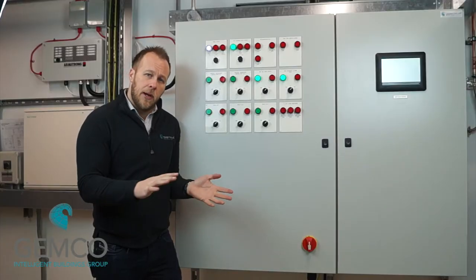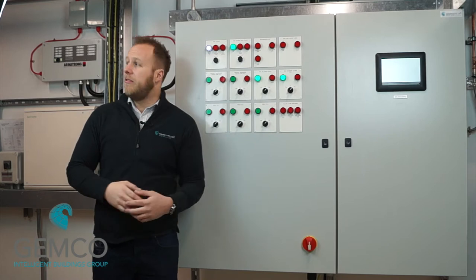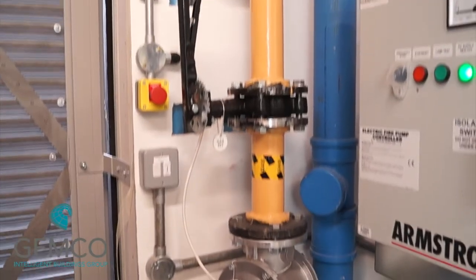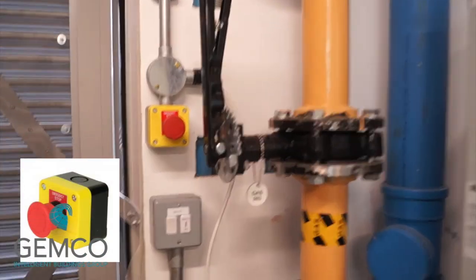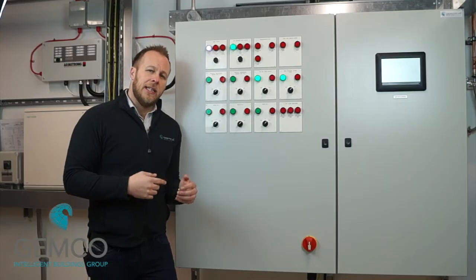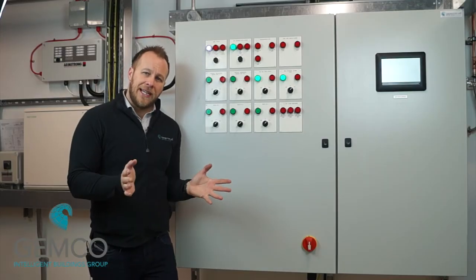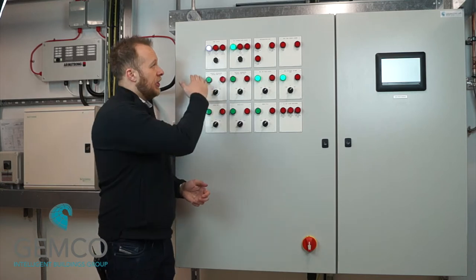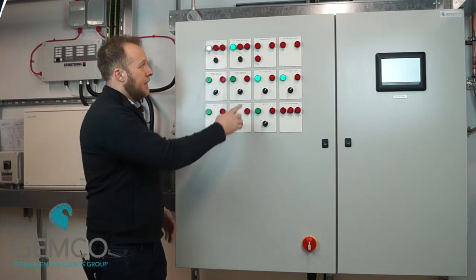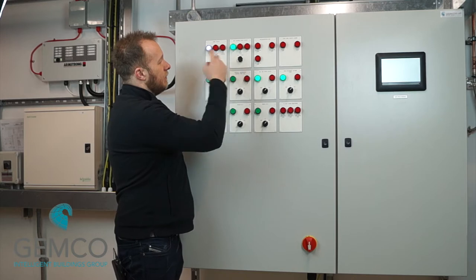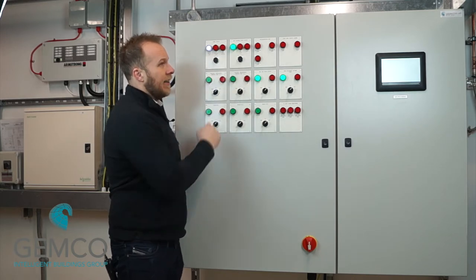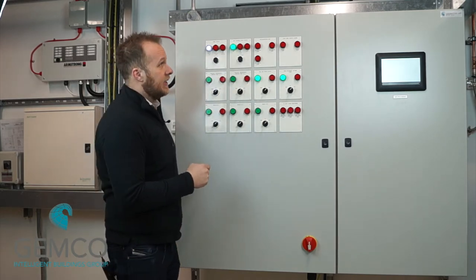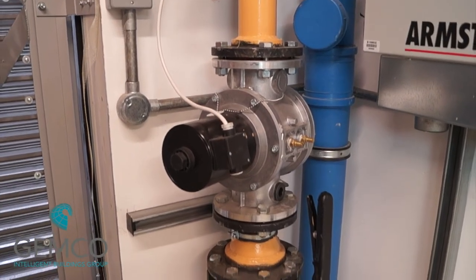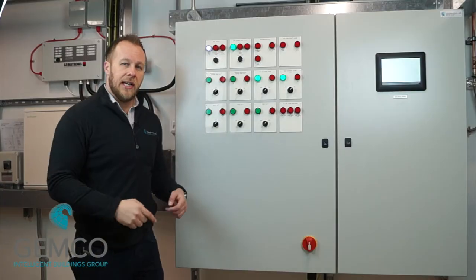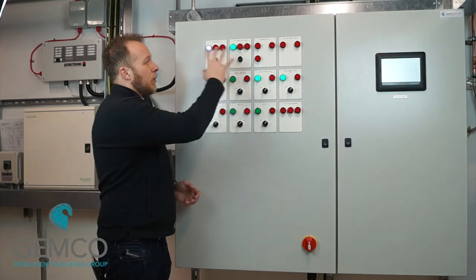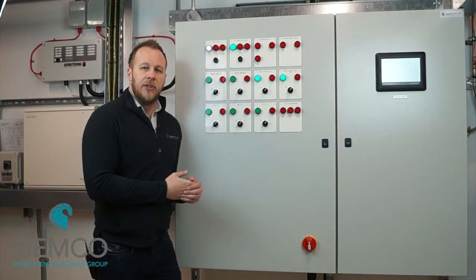So if there's a fire, it will melt the link, and that is wired in series with an emergency stop button at the entrance or the exit of the boiler room there. That is one continuous circuit, and if that circuit breaks, then we're going to shut the plant down. But if any of these life safety systems are ruptured, your gas valve will close. Now your gas valve is over there, the black valve on the yellow pipework there, and that will close to stop gas coming into the plant room.